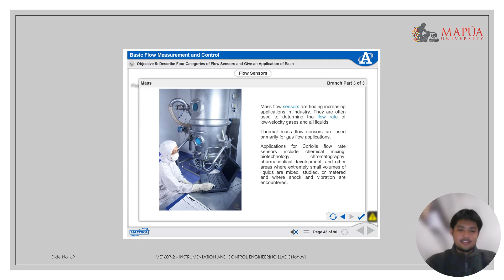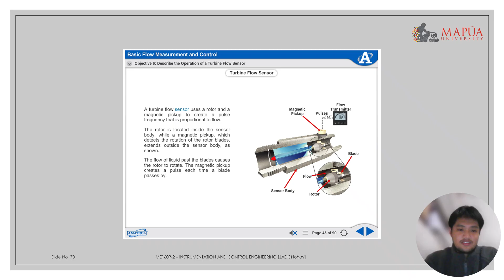and vibration are encountered. A turbine flow sensor uses a rotor and a magnetic pickup to create a pulse frequency that is proportional to flow. The rotor is located inside the sensor body, while a magnetic pickup, which detects the rotation of the rotor blades, extends outside the sensor body as shown. The flow of liquid past the blades causes the rotor to rotate. The magnetic pickup creates a pulse each time a blade passes by.